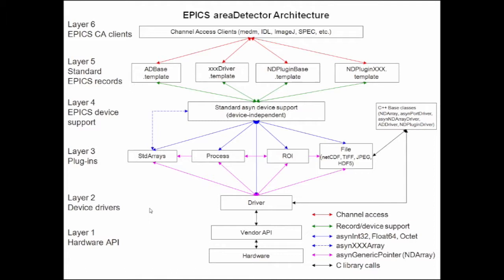A plugin, when activated and told to get data from the driver, registers for a callback, and every time the driver gets a new array it calls the plugin to do its processing. The plugins and the driver communicate through standard asyn device support to the EPICS records above — binary output records for starting/stopping acquisition, analog output or longout records for binning, and so on — using standard EPICS records through standard asyn device support, which is device-independent.